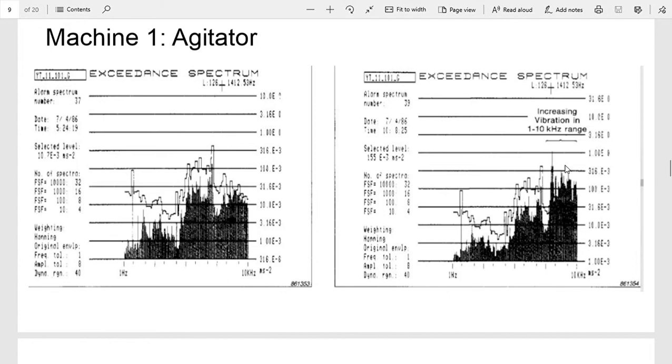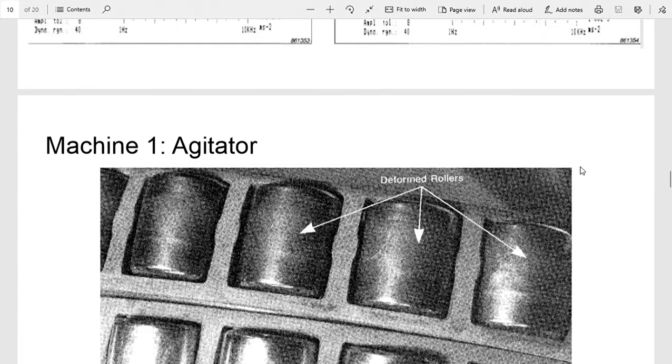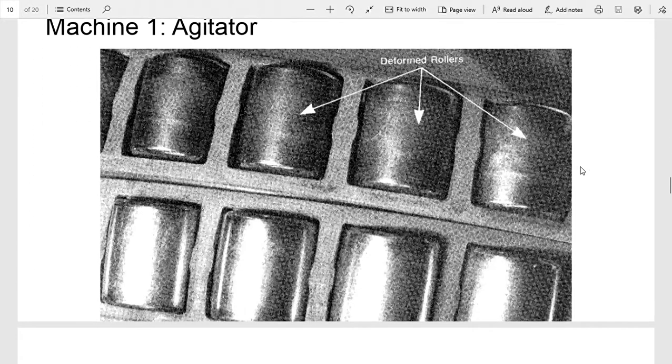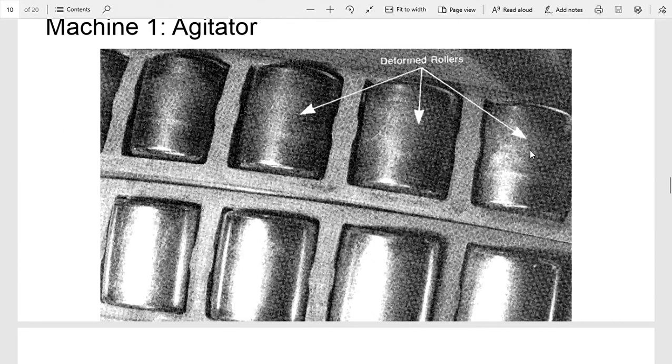So eventually they decided to stop production and pull the bearing off and reinspect it. They found that a bunch of the rollers were deformed. You can see there's these little flat spots all around them.